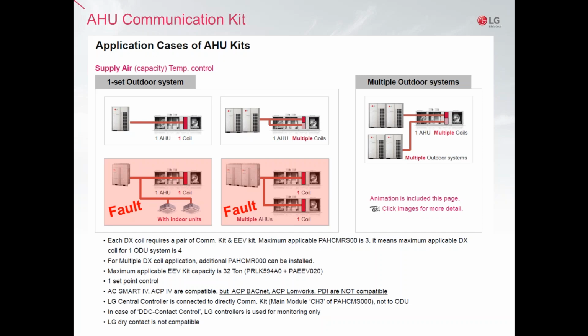Now, it's the turn of the supply air control configuration. Just a reminder, the supply air control is typically for DOAS or makeup units. As I mentioned, the three top configurations are basically the same as the previous slide. We have on top left the supply control one-to-one, with the same limitations on outdoor unit capacity, the one system to two or multiple coils, and also two systems or more to independent coils in the same air handling unit. The bottom configurations, which allow connecting other indoor units in the same refrigerant piping, are not allowed for supply air control systems. The reason is a bit technical, but in a nutshell, we cannot target two different discharge temperatures in the same system.